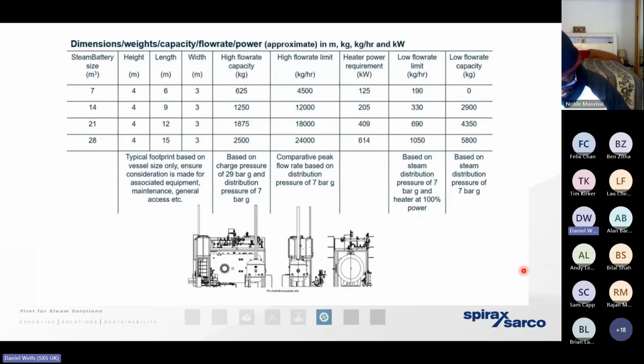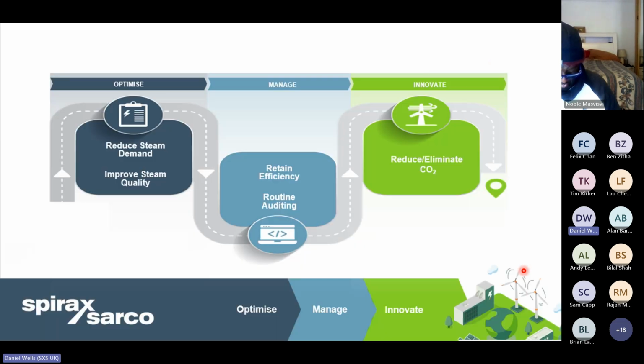There's no reason why steam batteries cannot be banked if there are multiple processes, but a steam battery traditionally works very, very well in partnership with an alternative source of energy, whether that be a gas-fired steam boiler or even an electrified steam boiler. So we really need to understand that the wrong thing to do would be to engineer that steam infrastructure, that alternative to natural gas, without having gone through the previous steps.